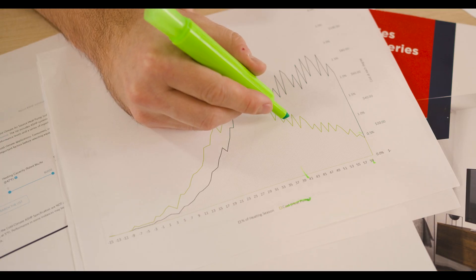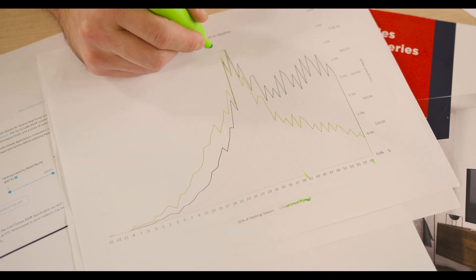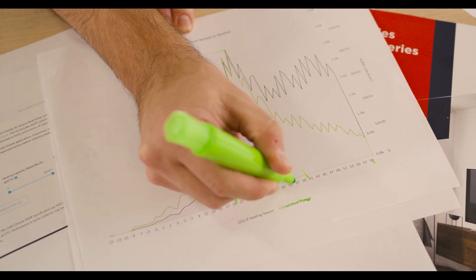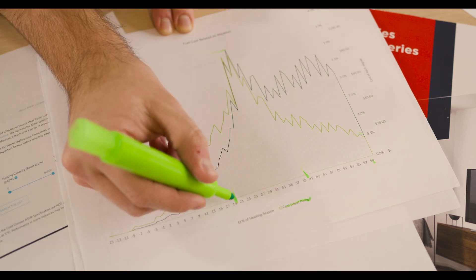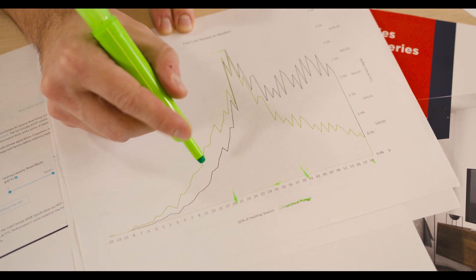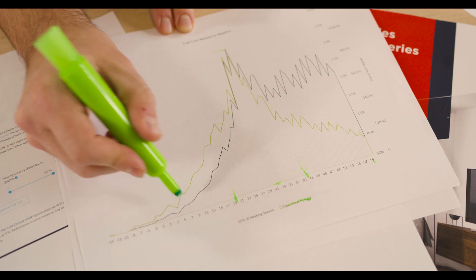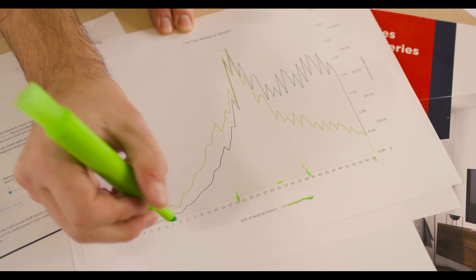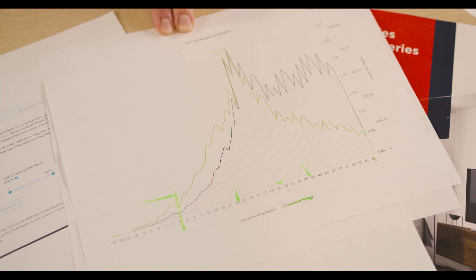As the temperature gets colder we'll see it peaks in how many BTUs are required, particularly between 20 degrees and 40 degrees — that's where we need to pay close attention to heat pump performance. As the temperature gets lower and lower the heat pump is using more energy, but that increase becomes very marginal and next to nothing once we reach down into the single digits.